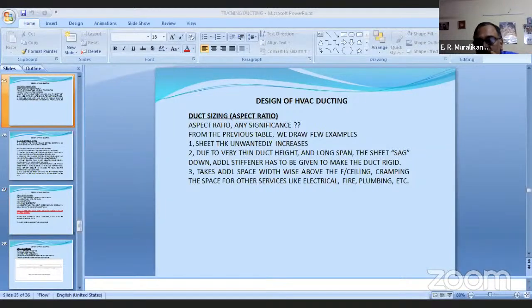In that case, suppose you have a 500 by 500 duct, you go for 550 or something higher in size. That's the only way, because you have to add the insulation thickness and the roughness of the insulation in the friction loss. And this formula is the same formula I showed you in the PowerPoint. I have not done any magic in that. It's a big formula. I can share it again. Not a big thing.